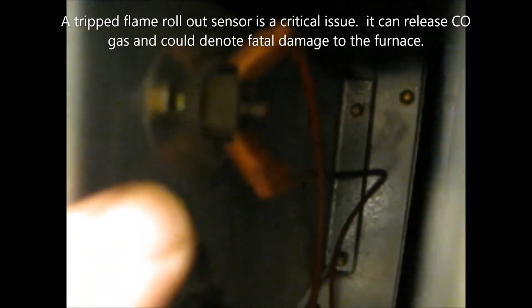Another safety switch is called the rollout, the high heat rollout switch right here. Now if fire were to leave the combustion chamber and settle in this area, heating up the back end of this combustion chamber, then this switch would be activated. Now the nice thing about this switch, it actually has a little button on it that you can reset. Another safety switch is way in the back there. That's another heat switch, and this is normally closed. And can be tested with an ohm meter. If you get a tone on your ohm meter, it's good. If you don't get a tone, that means it's open and bad. Same thing with your rollout switch. It is normally closed. If you're getting a tone, that is good. No tone would mean it's bad.